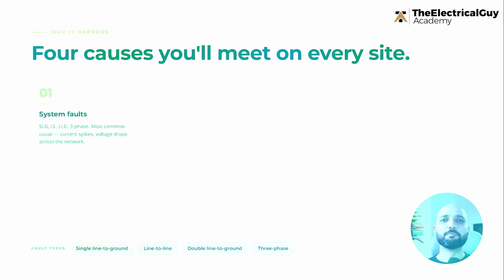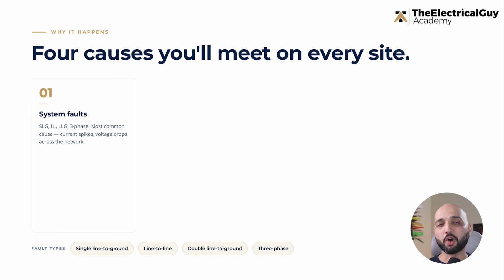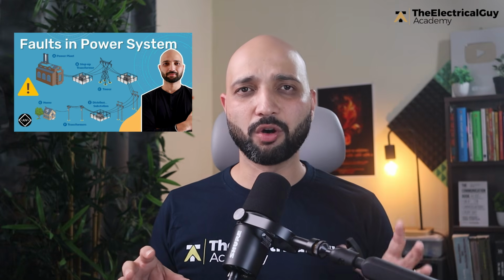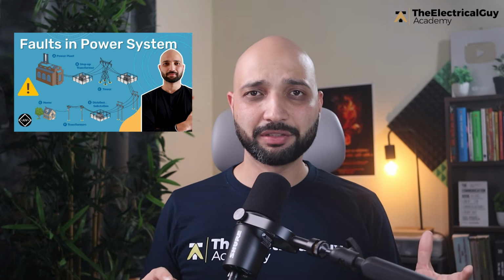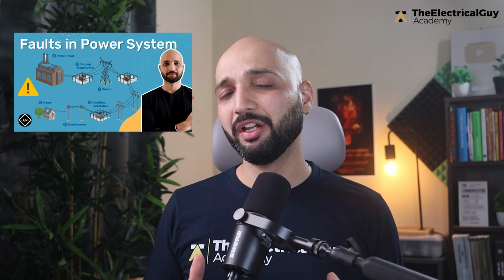Now, the next question is, why do voltage sags and interruptions happen? Well, the most common cause is a fault on the power system. A fault means an abnormal current path. It may be a single line to ground fault, line to line fault, double line to ground fault, or three-phase fault. And if you want to learn about the different types of faults and their severity in power system, I do have a dedicated video on that.